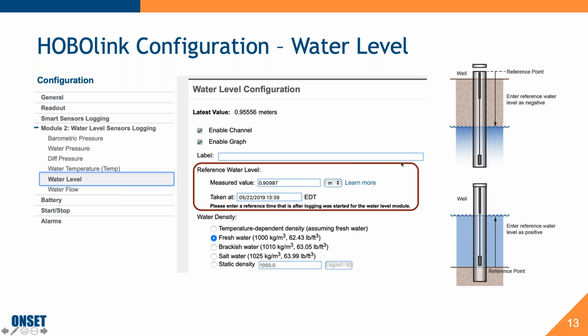This is where you'd enter your water level. I want to remind you that the reference will be negative or positive depending on where your reference is taken. If your reference is taken above the sensor—say the sensor is down in a well and the reference is the top of the well—then the reference should be entered as a negative value. If your reference is taken at the bottom of the well and the sensor is above it, the reference is positive. This is the easiest way of entering a reference water level ever—you just put it in, find the date it was taken, and HOBOlink will catch the most recent data point next to that as your reference.